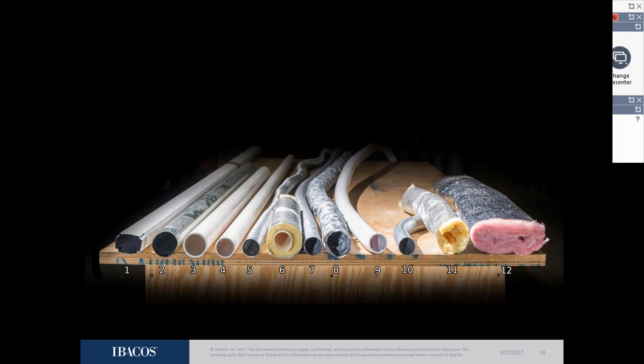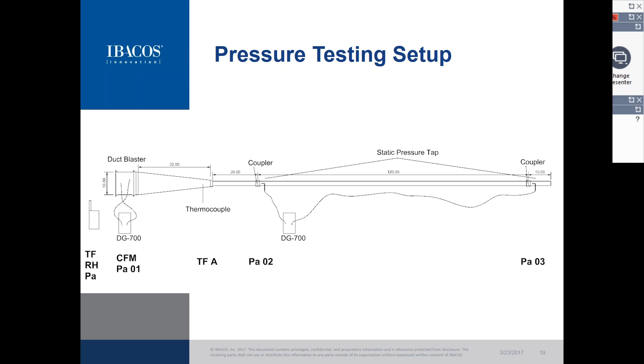Here's an image of our pressure testing setup, based on ASHRAE standard 120 for understanding the flow resistance of HVAC ducts. At a basic level, we had a fan measuring the airflow, and using a manometer we were able to measure the static pressure loss along a test specimen.